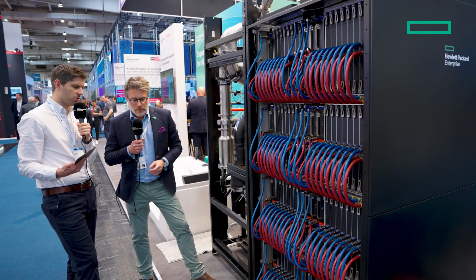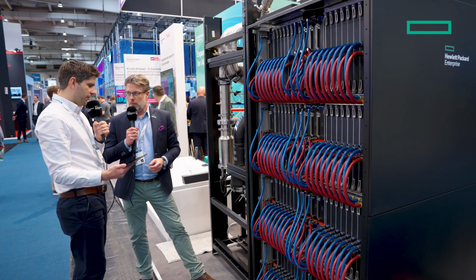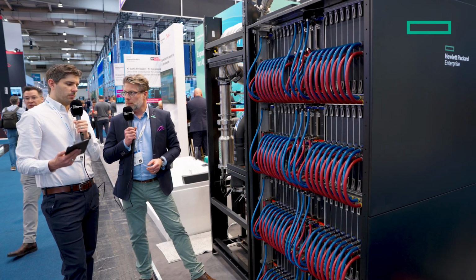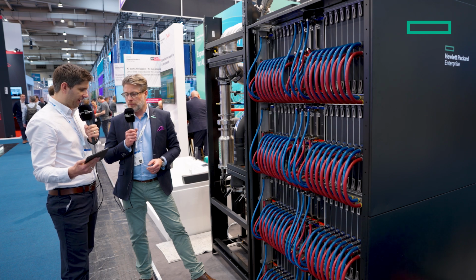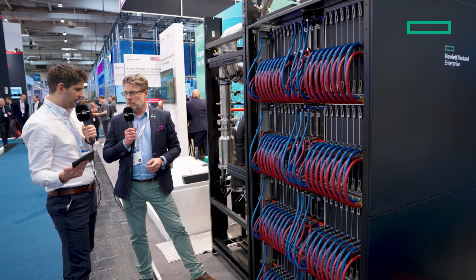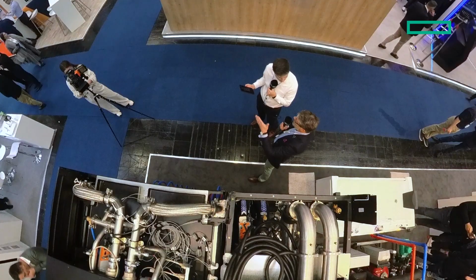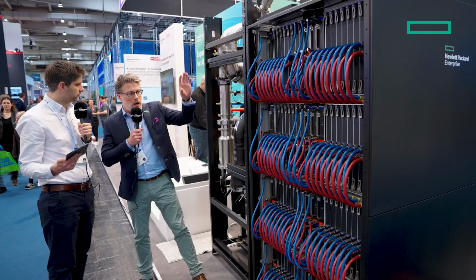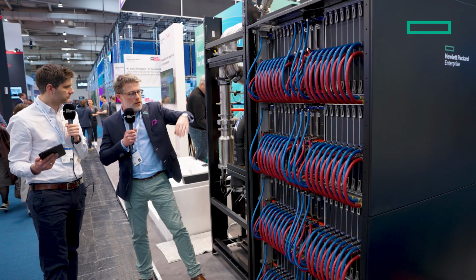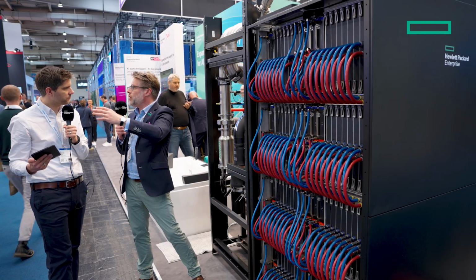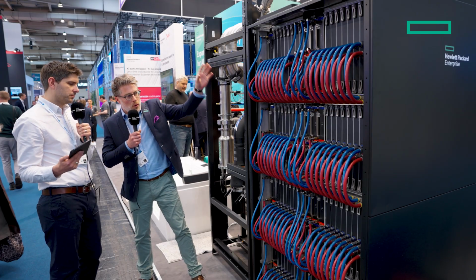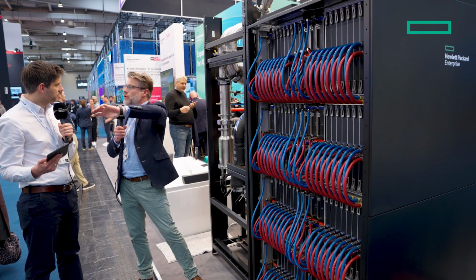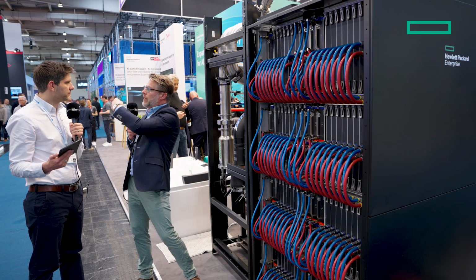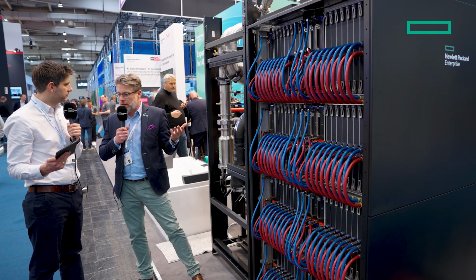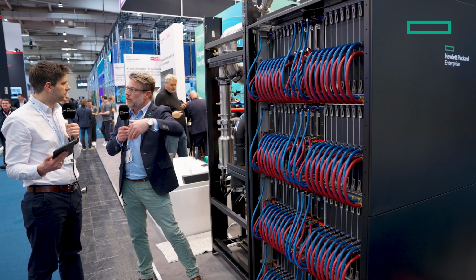Usually with an air-cooled server, an air-cooled data center kicks out hot air from the fans, and then you try to cool it with air conditioning to keep it cool. However you do that, you try to bring the heat exchanger as close as possible to the air-cooled rack - whether it's a water flooded back door, a side cooler, or air conditioning in the room - you're bringing the heat out of the air into a liquid media, and then you transport it through your data center. Usually, classically in all data centers, you spend more energy to just cool it off in the air.